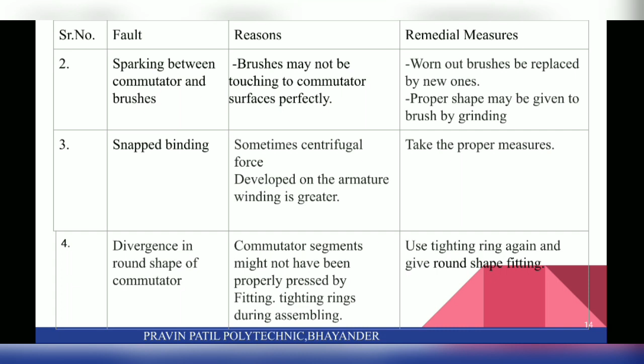Fourth fault is divergence in round shape of commutator. Reason for this fault is commutator segments might not have been properly pressed by fitting tightening rings during assembling. And remedial measure is to use the tightening ring again and give round shape fitting.